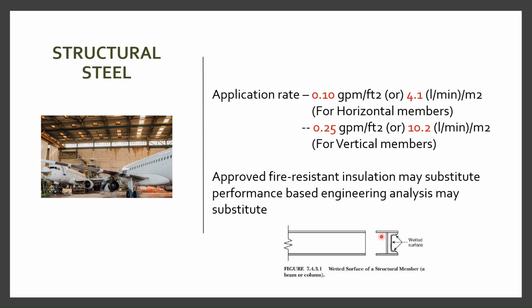This mistake should not happen in your particular project. However, please note, for horizontal members the application rate would be 0.1 GPM per square feet. For vertical members it should be 0.25 GPM per square feet, and it all depends on whether we require a water spray system or not, based on project specification requirements. But in most cases, aircraft hangar beams, or exposed beams, shall be protected with a water spray system.